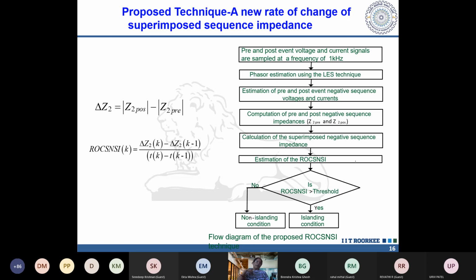Then we took the rate of change of the superimposed impedance. We got some value. If it crosses a certain threshold, we declare that the AC microgrid is disconnected from the main grid. If it is below the threshold, we declare that it is not disconnected.